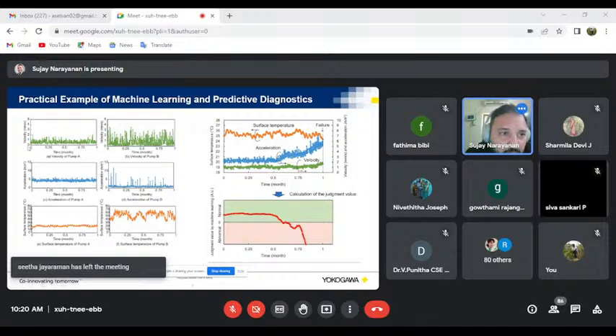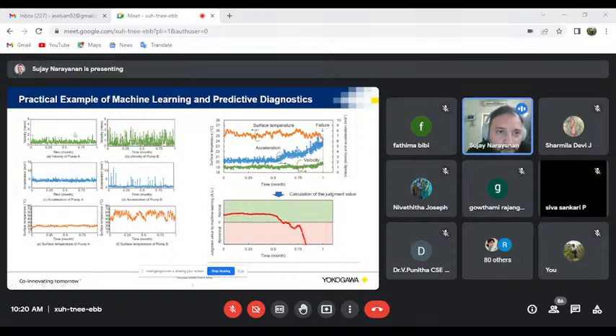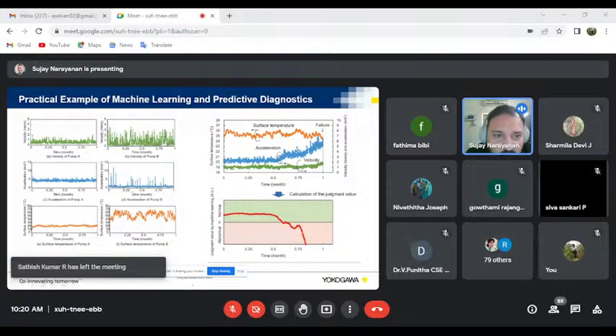So if you can see here, this is the velocity of pump A and the velocity of pump B. It's another pump, two different pumps. Okay, let's take one thing. And then you have the acceleration of the pump. This is nothing but the vibration. And this is the surface temperature of the pump. This is a very healthy surface temperature because you can see it's more or less constant. But if you see pump B, you have too much velocity and too much acceleration, vibrations up and down.